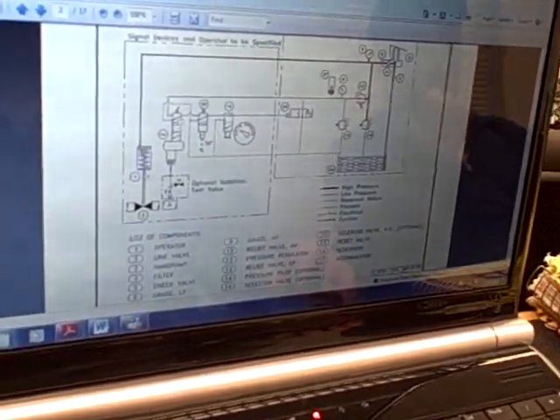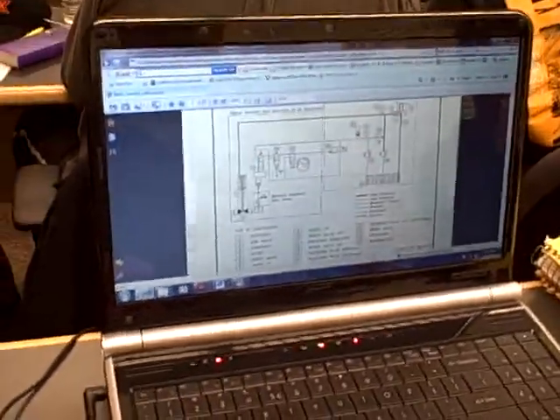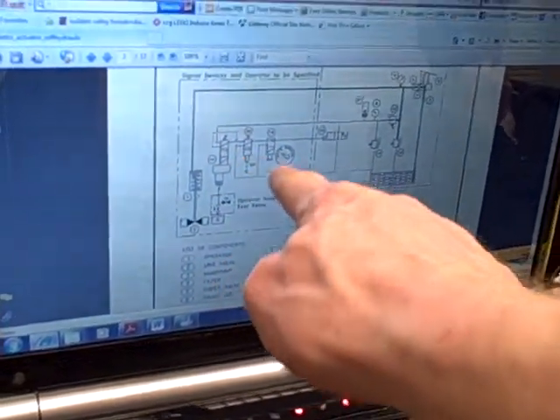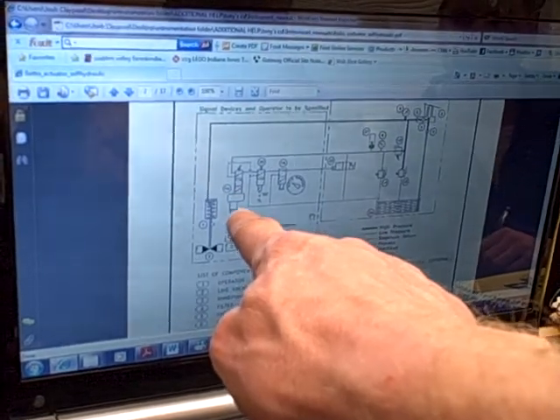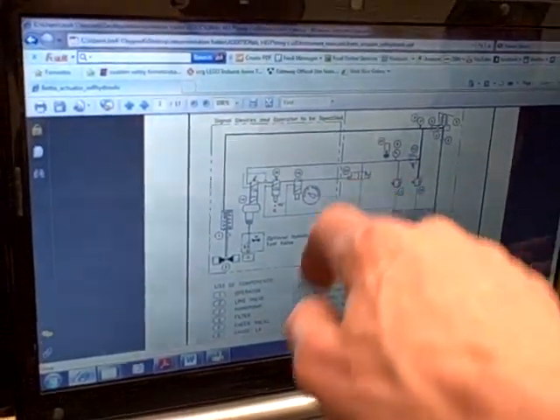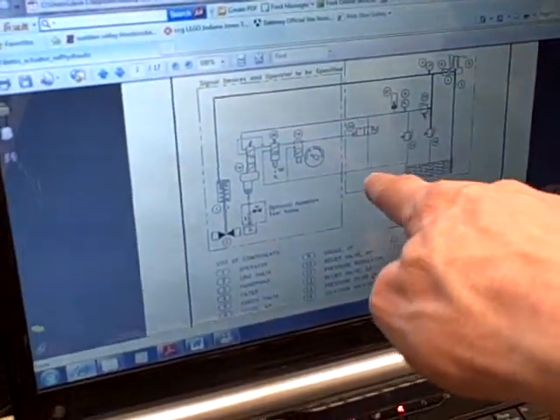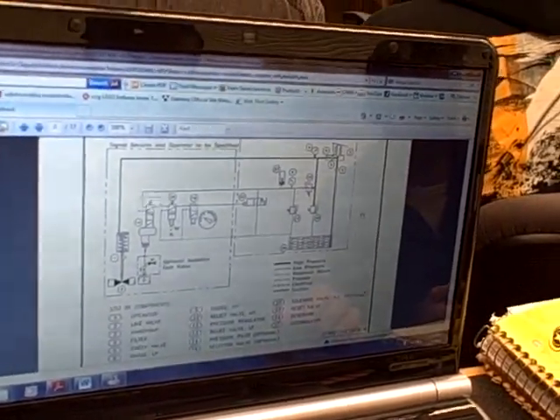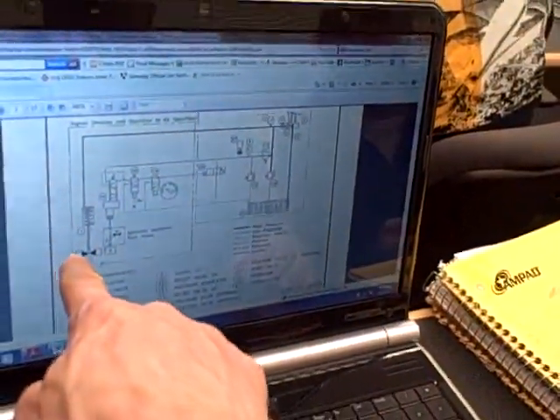My question is, when this fails — low pressure or high pressure, whichever — it dumps everything in here. How do we then change the pressure to get that? If any of these go to their fail states, whether you switch that off or you lose power or you get too high or low pressure on the line, we dump pressure going to that little actuator on 23. That opens the valve block, which connects what used to be a pressurized line. This regulates the pressure, so what happens is this pressure wants to stay the same, dropping this pressure — it drains it all. All the pressure drains down to nothing, and when that happens, that shuts.